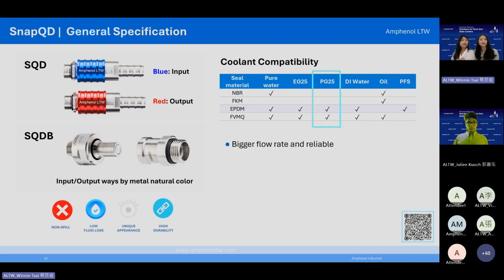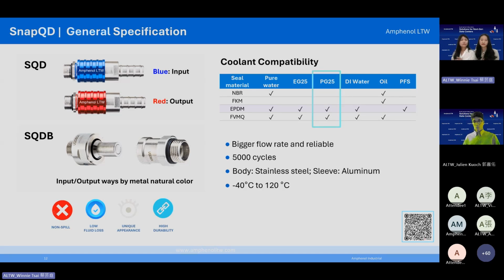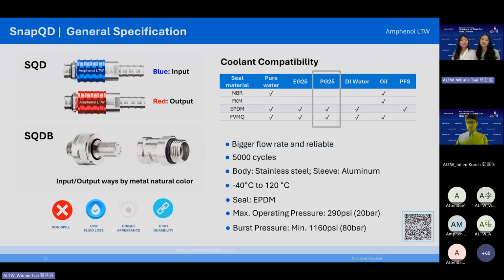High stable flow for reliable cooling. Durability tested to 5,000 cycles. The material of the body is stainless steel, and the sleeve is aluminum. The operating temperature is from -40 to 120 Celsius degrees. And the material of the seal is EPDM. The maximum operating pressure is up to 20 bar, and the maximum burst pressure is 80 bar. And all of these pair with our flat face non-spill design to keep fluid loss low and uptime high.